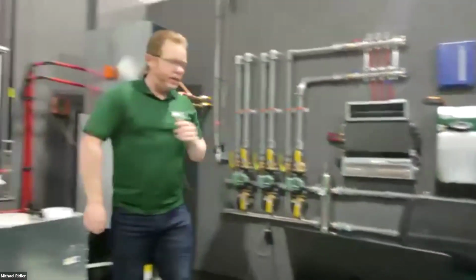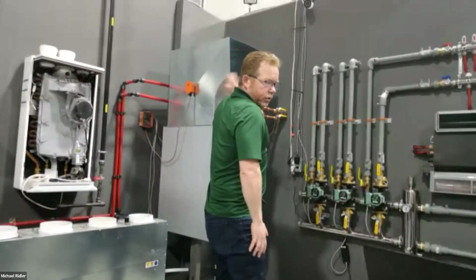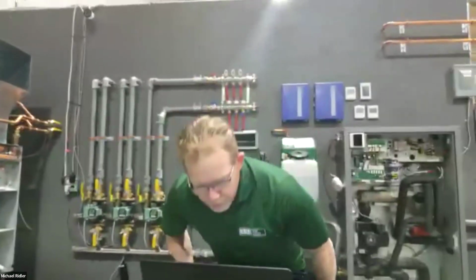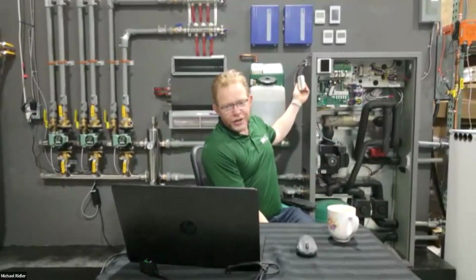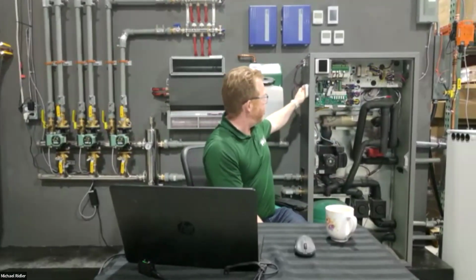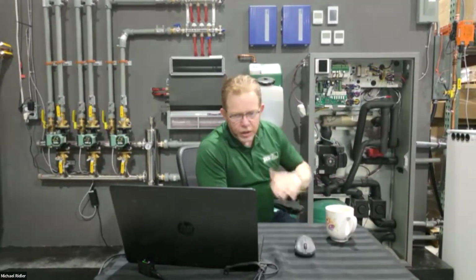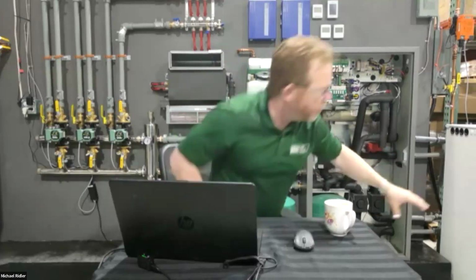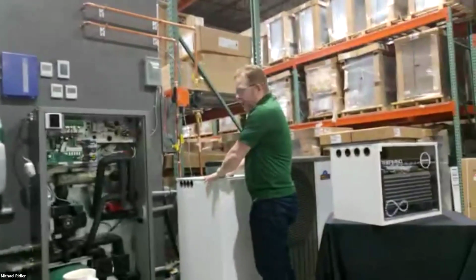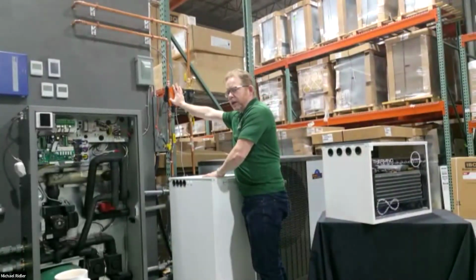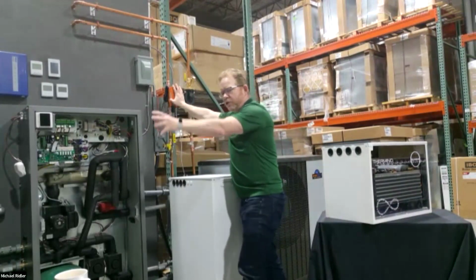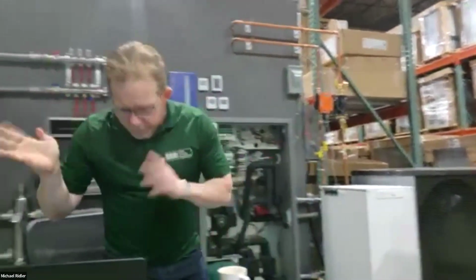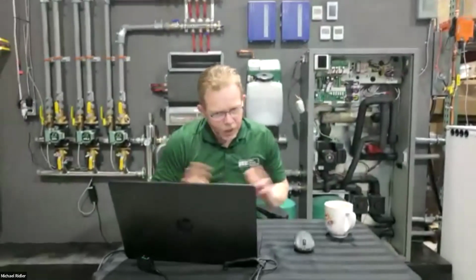Over here, where you can't see, I have a 5-ton air handler that's charging the battery. That Measurement Canada meter measures it—this little dongle with double-sided tape isn't working so good, guys, but the rest of the lab's pretty cool. It reads and writes all the data off this unit. So I'm seeing how many BTUs, how much flow, and what the compressor RPM is feeding into this battery, and then I'm using the Measurement Canada certified meter from Belimo to actually measure the discharge of the battery.